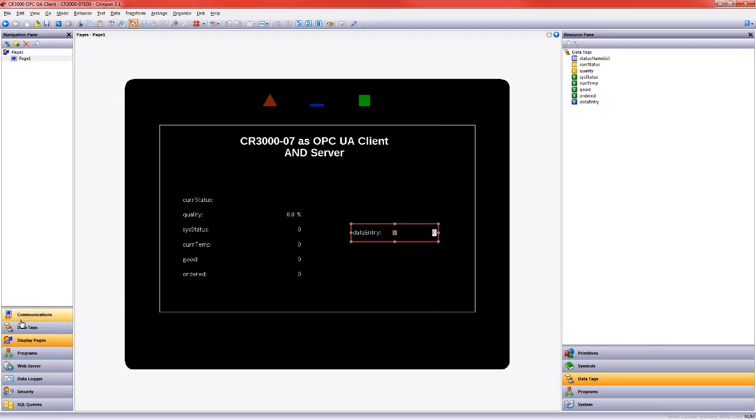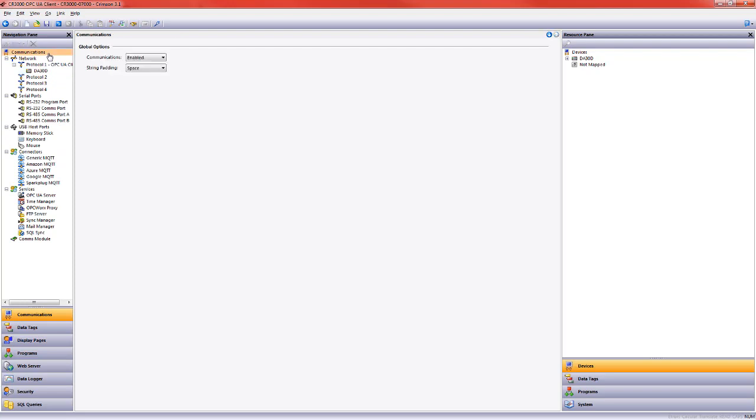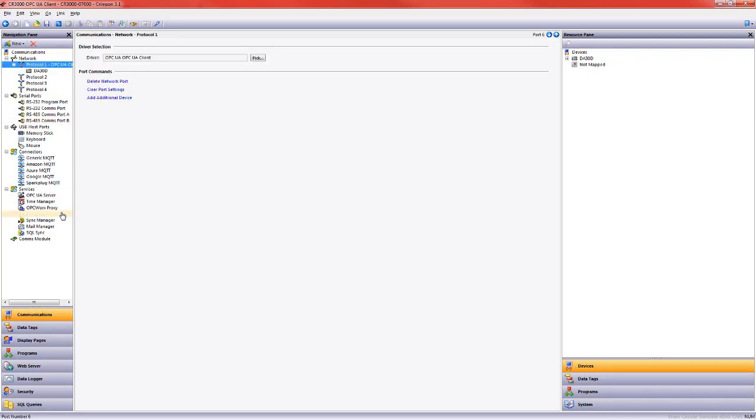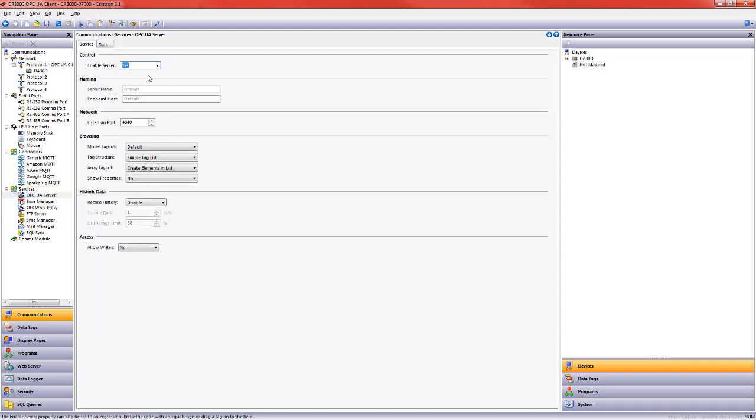And now let's just quickly set this up as an OPC UA server. So I'm in the communications, we can see it's already set up as a client. I'm going to come down to OPC UA server. How simple is it? It's this simple. I'll just choose yes. And I don't need to change any defaults here.